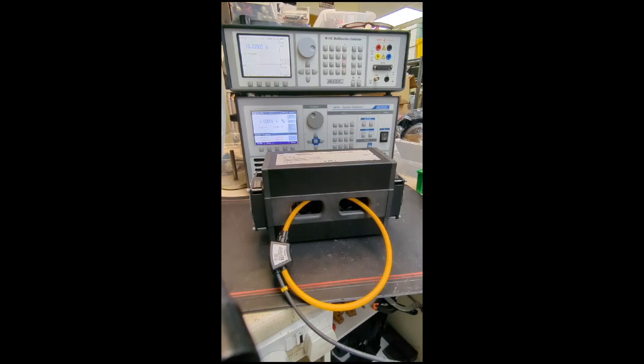Now, one consideration with this particular device is things like the positional sensitivity. It's geometrically calibrated, so regardless of the position of that coil, and this particular family of Rogowski coils, they have excellent positional sensitivity and accuracy. So the bottom line is, we're always comparing these to international standards. We have a calibrated source there.